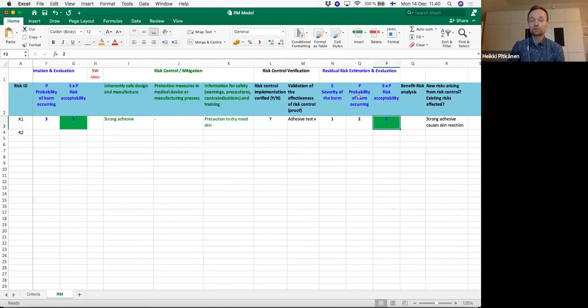You do some additional testing on how the electrode sticks on the skin, and you verify that this has been implemented. You refer to a test report that you have made, and you do the estimation of the residual risk. The severity cannot come any lower than 1. The probability of the harm might come down a little. We came up with a new number, and in this table it might look like this. So we're talking about a minor risk, but it might be very relevant from the business perspective. And then you might need to do some benefit-risk analysis on this particular line of thought on your controls. You might come up with an answer that is somehow positive. I just put a plus there.